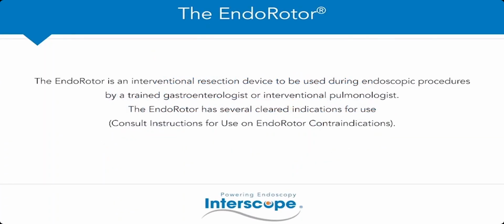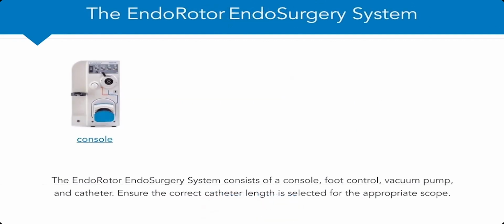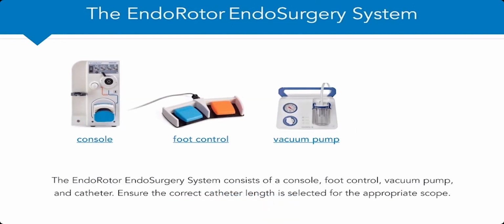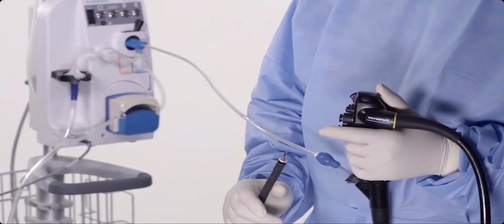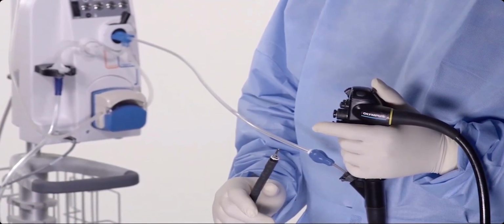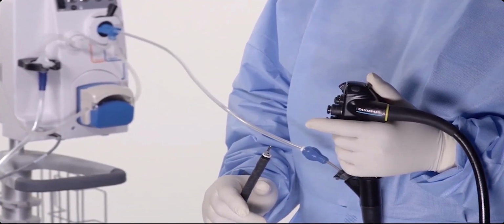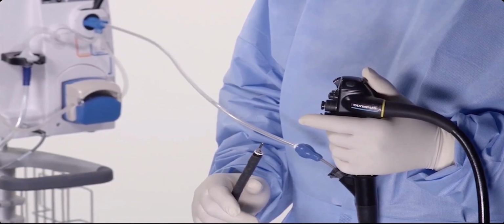The EndoRotor is an interventional resection device to be used during endoscopic procedures by a trained gastroenterologist or interventional pulmonologist. The EndoRotor has several cleared indications for use. Consult instructions for use on EndoRotor contraindications. The EndoRotor endosurgery system consists of a console, foot control, vacuum pump, and catheter. Ensure the correct catheter length is selected for the appropriate scope. The catheter requires a 3.2 millimeter endoscope working channel. If you have additional questions on the catheter selection, please consult the EndoRotor instructions for use endoscope compatibility chart.